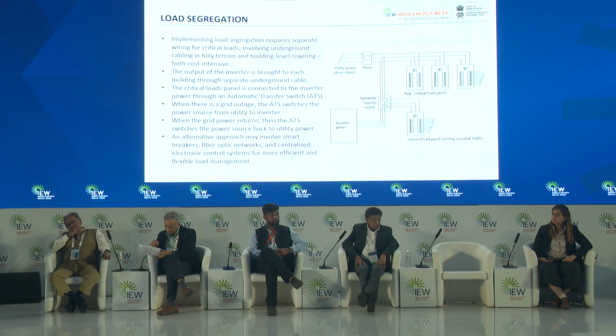Then we would disconnect the subcritical loads, and then we would try to provide power to the critical loads for as long as possible. So to implement the load segregation, what we have are critical load panels. We would have separate circuits for the critical loads, and there would be an ATS, an automatic transfer switch, which would switch to the critical loads during outages. So this is pretty extensive work, which requires a lot of underground cabling and rewiring.